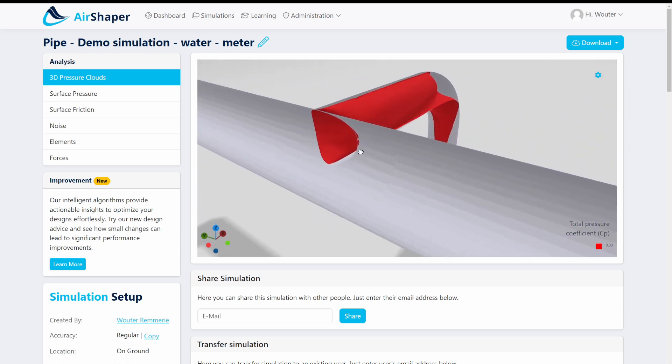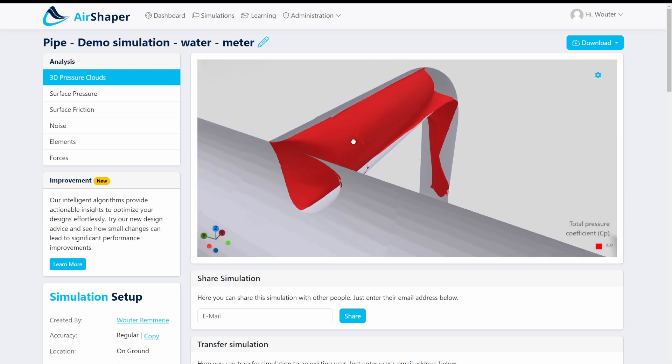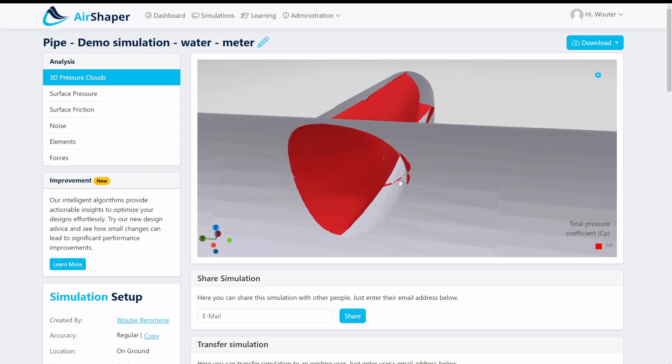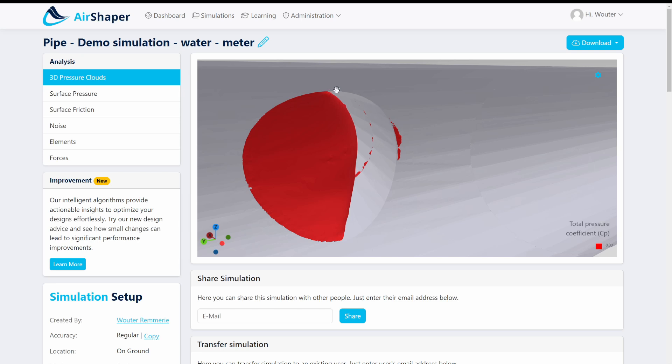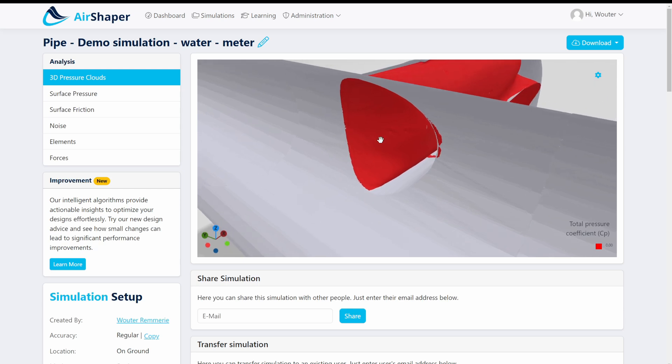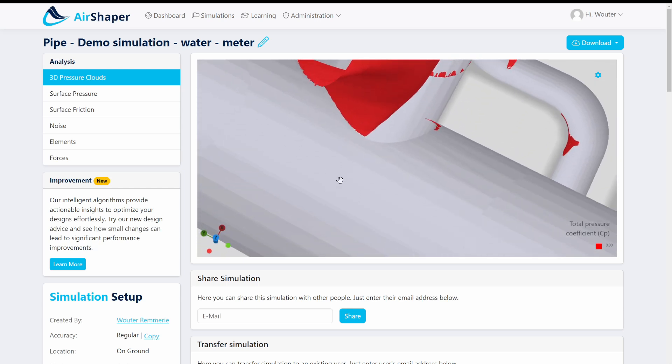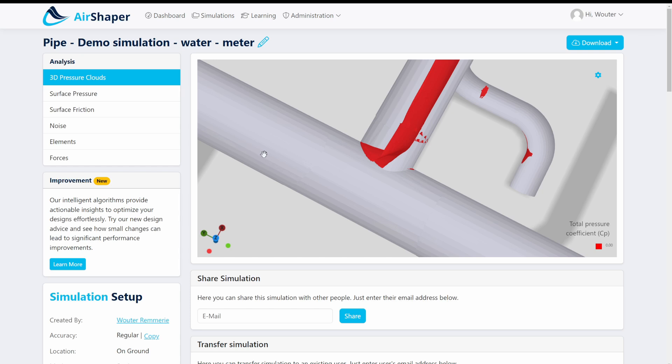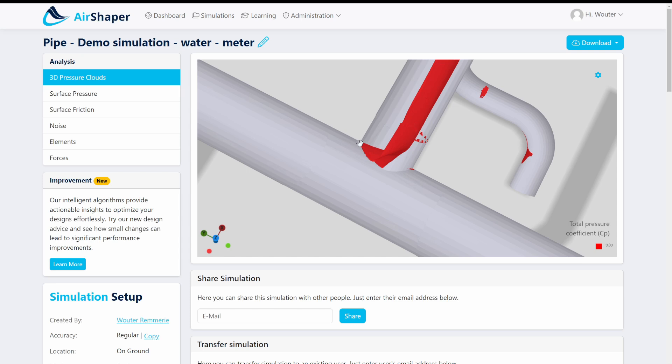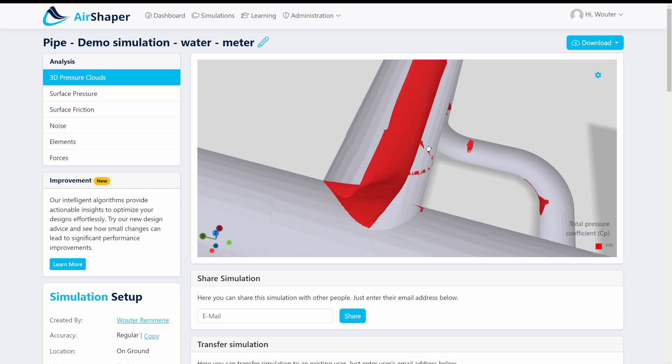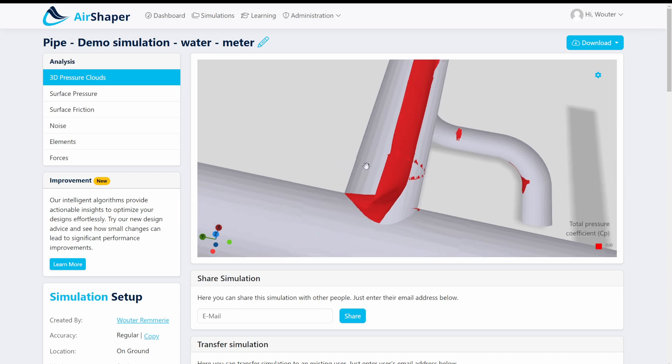This one is quite interesting because over here what we see is that this 90 degree bend, it's a very simple pipe network so what you see here is that the junction between this pipe and this pipe is just the same as having two cylinders intersect so you get this very sharp edge 3D curved edge between the two pipes. This means that the flow coming through the main pipe wants to continue on a straight trajectory so the part of the flow that actually wants to go inside this 90 degree side branch of the network needs to curve around the sharp edge and this edge is way too sharp. So there's no possible way that the flow can actually make this sharp corner here so it'll take a longer route like this and hit the side flank here and you'll get a lot of separated airflow or water flow in this case.